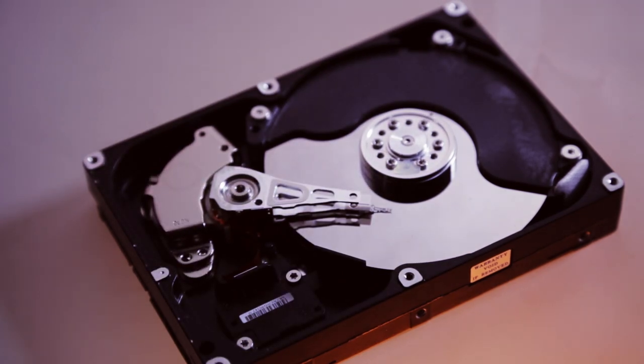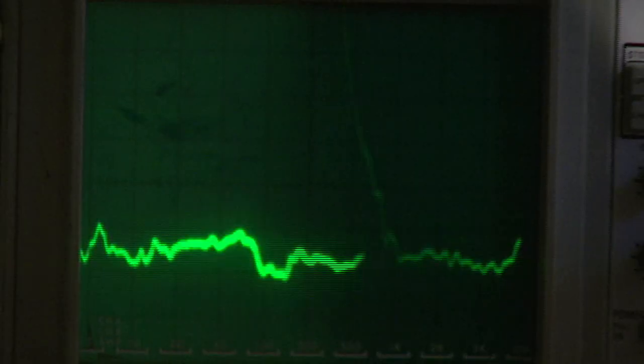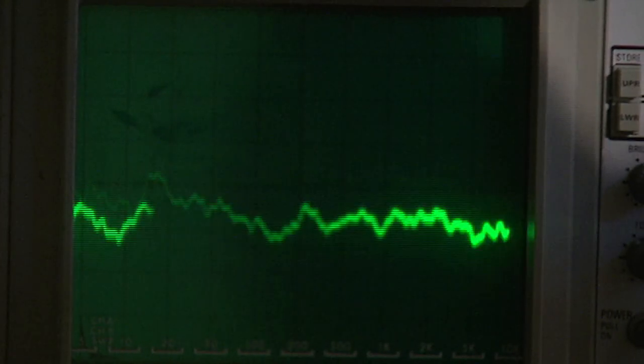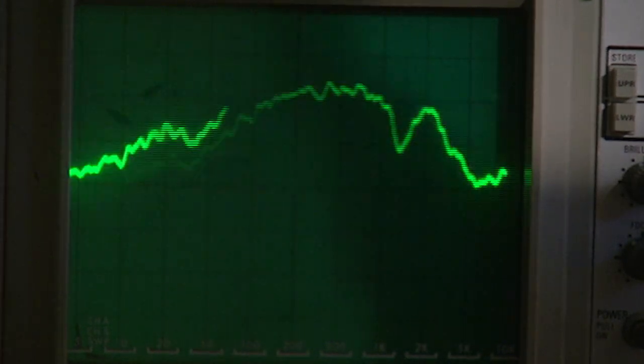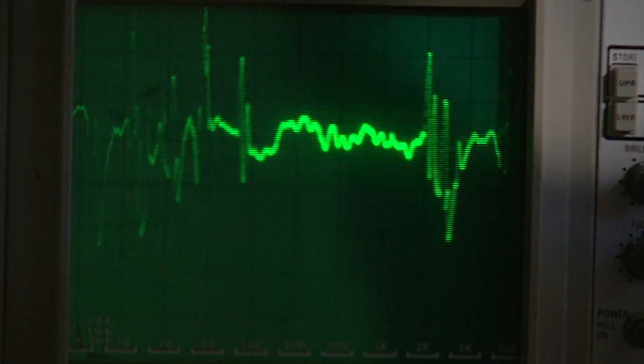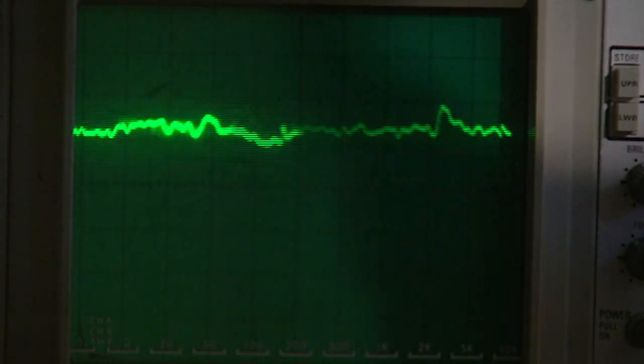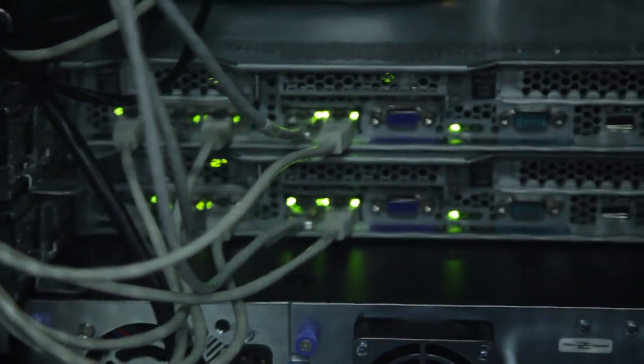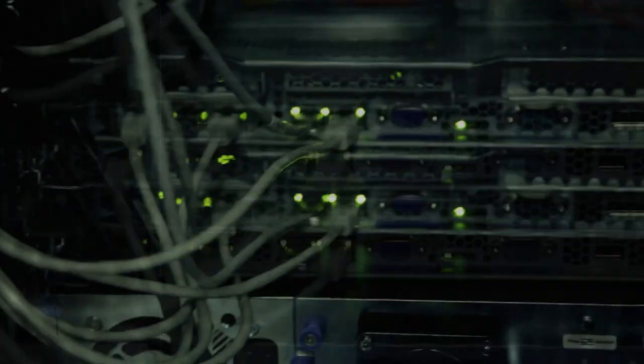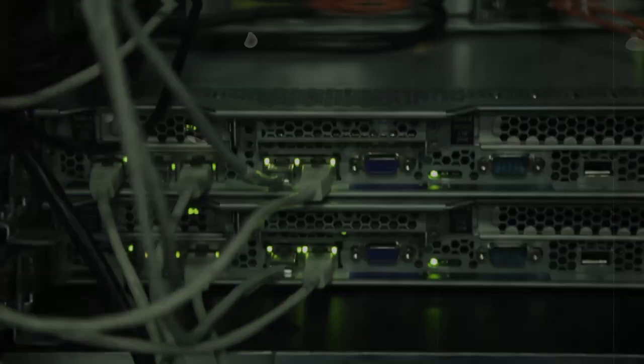Modern hard disk drives have proven to be sensitive to the sound energy produced during a dry extinguishing discharge. Malfunctions can range from automatic shutdowns to more severe disturbances with a corresponding loss of data.